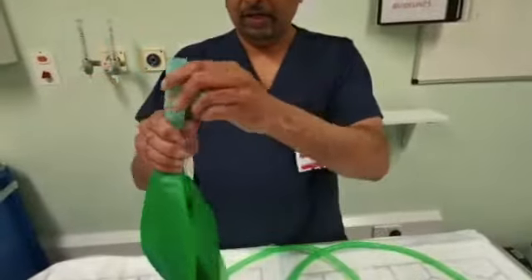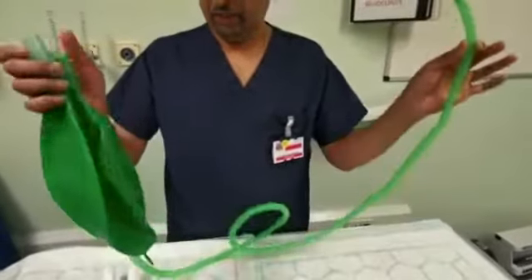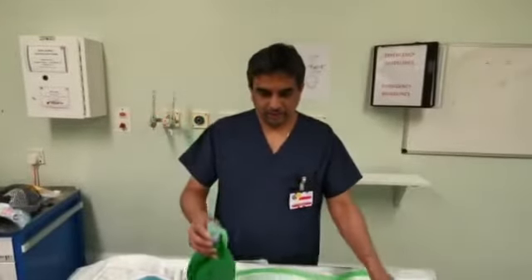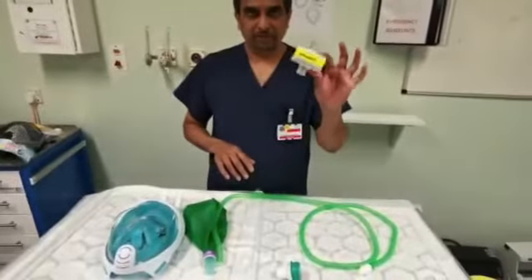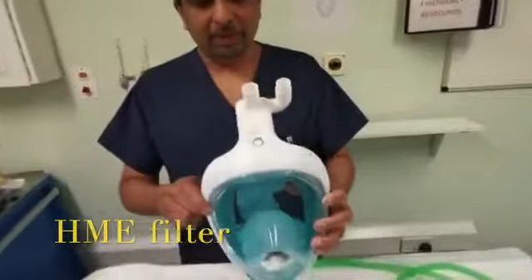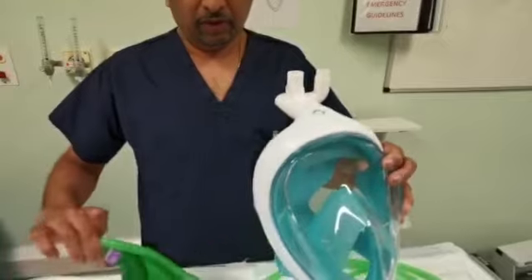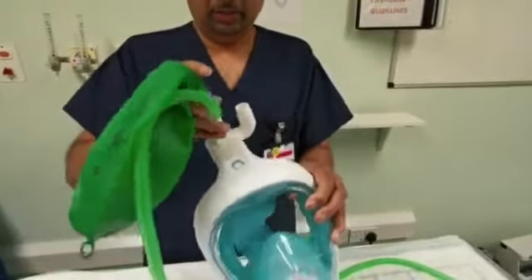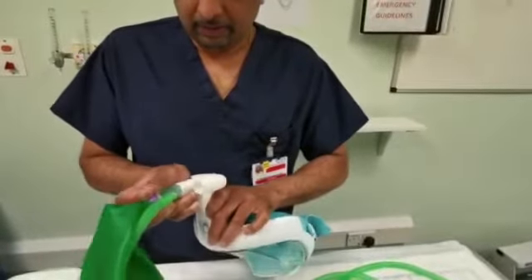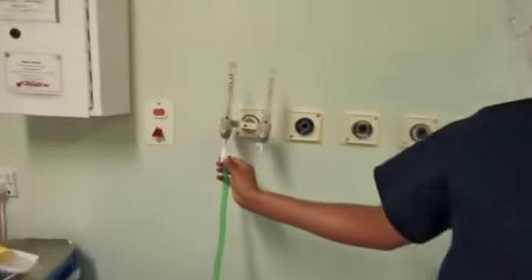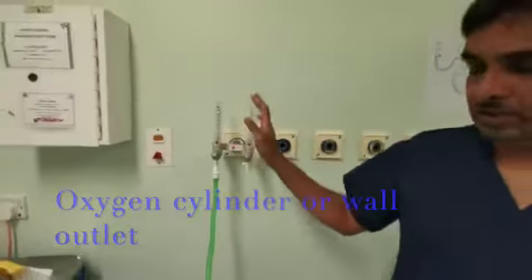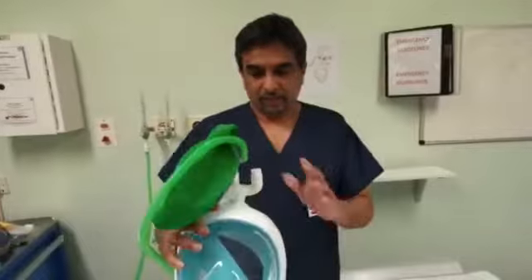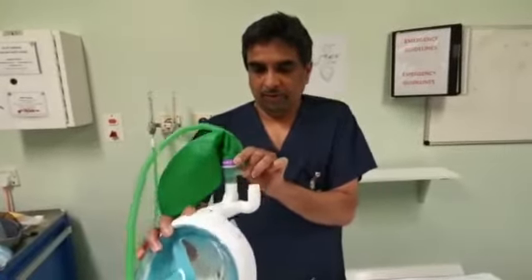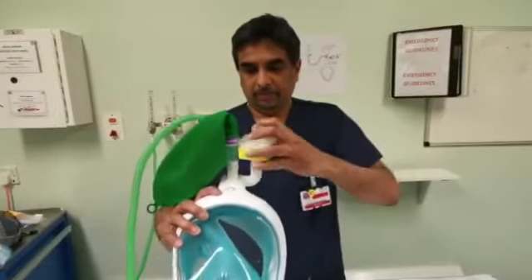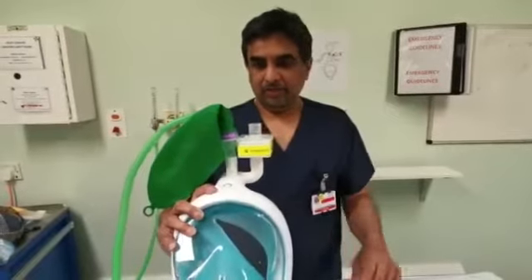This is the APL valve, and this is the T piece which you don't need. I'll leave it away. Then you're left with your oxygen tubing and the reservoir bag. Apart from the disassembled Waters circuit, you need a filter, which is a standard antibacterial filter. Coming back to the mask, you put your reservoir bag with oxygen tubing onto your inspiratory port. You connect it this way. The connector on the other end of the tubing goes onto the oxygen supply, which can be turned up. You can use either the wall or cylinder oxygen supply. Then at the expiratory port, you put the antibacterial filter on it. It sits that way, so it keeps the atmosphere clean.